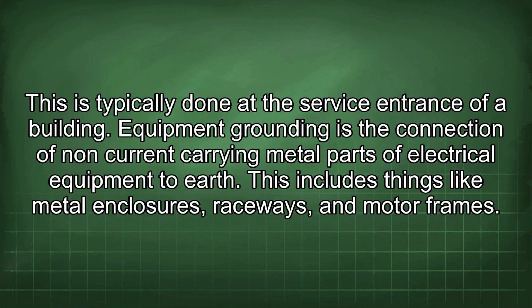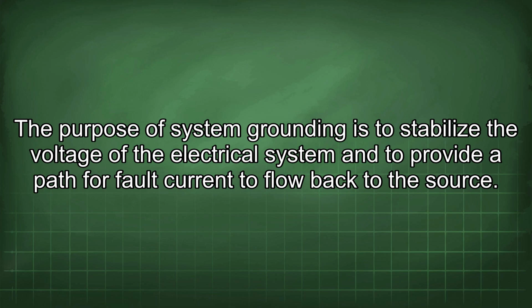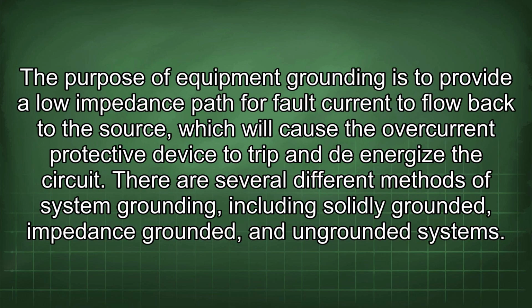This is typically done at the service entrance of a building. Equipment grounding is the connection of non-current carrying metal parts of electrical equipment to earth. This includes things like metal enclosures, raceways, and motor frames. The purpose of system grounding is to stabilize the voltage of the electrical system and to provide a path for fault current to flow back to the source. The purpose of equipment grounding is to provide a low impedance path for fault current to flow back to the source, which will cause the overcurrent protective device to trip and de-energize the circuit.